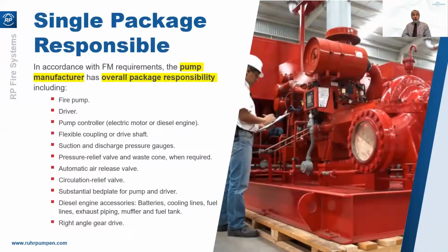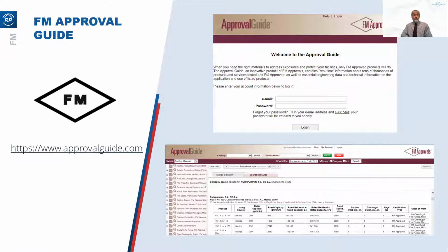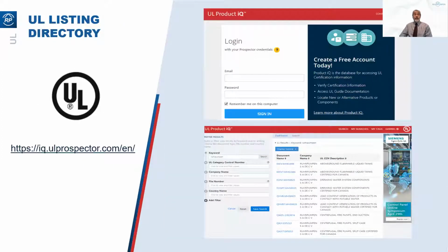Now, as part of the certification, we are required to assume total package responsibility. So we are responsible for diesel engines and controllers. We take total unit responsibility. So not just any Tom, Dick, or Harry can set themselves up as a pump packager. You're basically limiting yourself to the major fire pump listed companies. Here is the FM approval guide, and here is the UL directory. They are free for you to register. You can register for free and be able to look at any manufacturer to check their listing status.